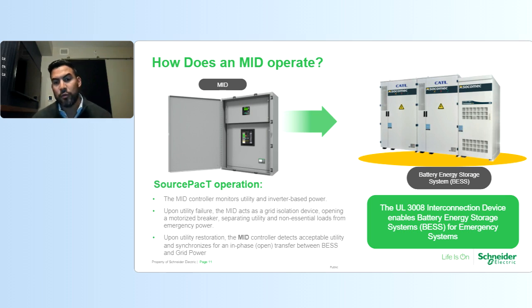And this is the UL 3008 listing, which is important in this marketplace as energy storage systems have commercialized. They're readily available. And if you want to use an energy storage system for an emergency application, the National Electrical Code requires some type of UL listed product, like a transfer switch, specifically designed to isolate from the grid and enable that energy storage system for emergency power. And we'll go through the UL 3008 listing criteria, but it goes through a significant amount of testing to ensure that it's specifically designed to open and close with the utility to enable that energy storage system for backup power.